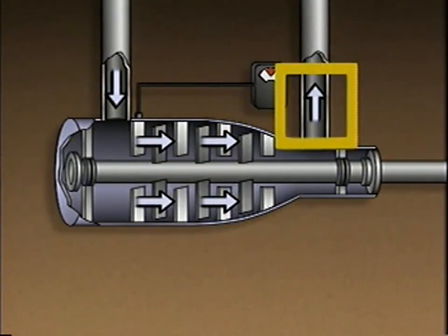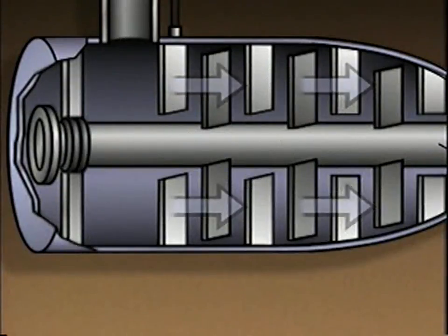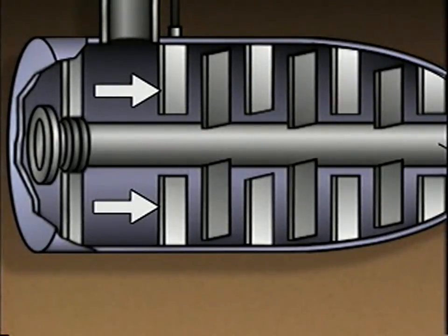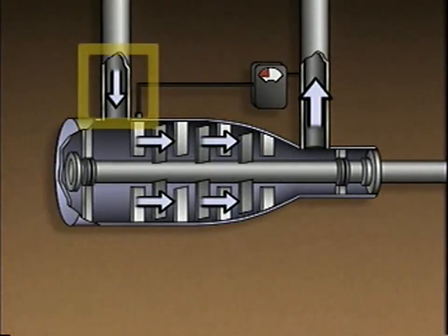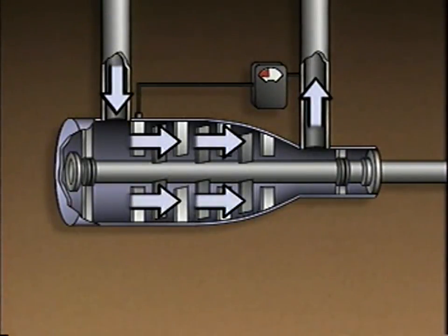When the demand for gas increases, discharge pressure begins to drop. The pressure controller responds to the change in pressure by opening the inlet guide vanes. When more gas enters the compressor, more gas can be compressed. As more gas is compressed, the discharge pressure increases until it returns to its desired value.